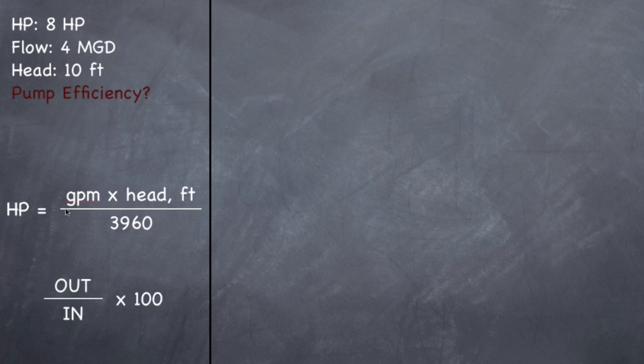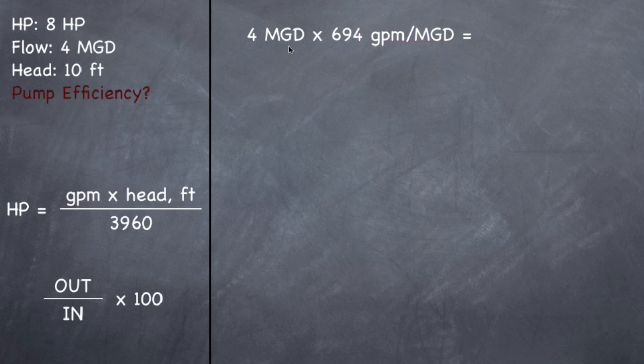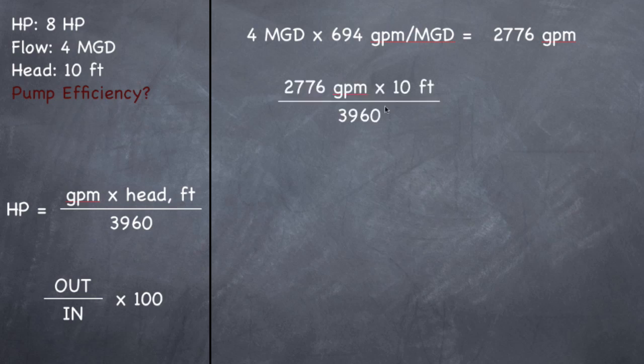Since it's an efficiency problem, you find the output divided by what it's supposed to be, then multiply by 100. So 4 MGD times 694 gallons per minute per MGD gives 2,776 gallons per minute. Then 2,776 times 10 feet divided by 3960 gives you 7 horsepower.